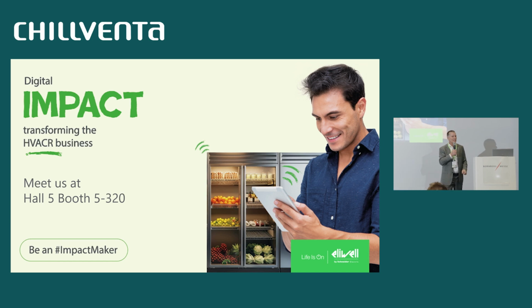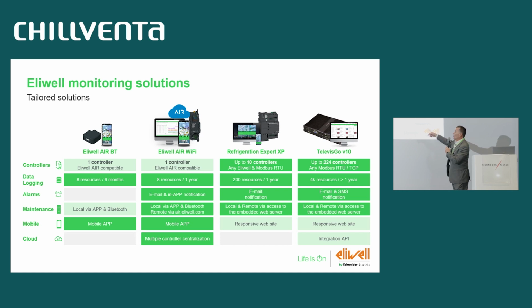Thank you for the question. Yes, if we look today at the two highest level models, we have an open protocol and also what we call an open driver. So it's actually possible to write the description of the controller, whatever it is, an energy meter, an HVAC controller, or refrigeration controller, in order to be represented and managed by the system. Real-time values, parameters, commands, whatever category, can be written into a file that is compiled and fed to the system, and this can be done by the user itself. There are some rules and a compiler that checks the validity of this data.